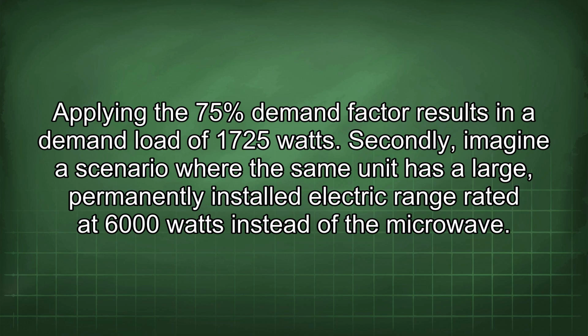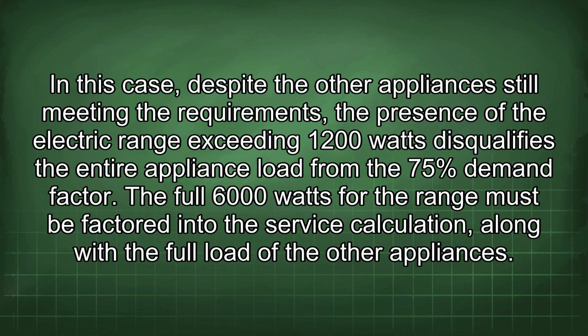Secondly, imagine a scenario where the same unit has a large, permanently installed electric range rated at 6000 watts instead of the microwave. In this case, despite the other appliances still meeting the requirements, the presence of the electric range exceeding 1200 watts disqualifies the entire appliance load from the 75% demand factor. The full 6000 watts for the range must be factored into the service calculation along with the full load of the other appliances.